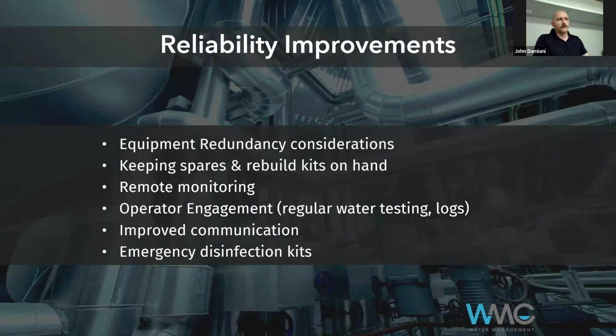Super important: operator engagement, regular water testing on site by your own staff, keeping logs, and having a system of communication where anything out of line is reported to the water treatment company. Really important, because that allows you to respond faster. Interruptions are going to occur — it's really about identifying those and getting them corrected quickly. That's what's really going to pay off in terms of the lifespan of the equipment, making sure you don't run out of spec for a long time — that's how you risk forming scale or having bad corrosion events.